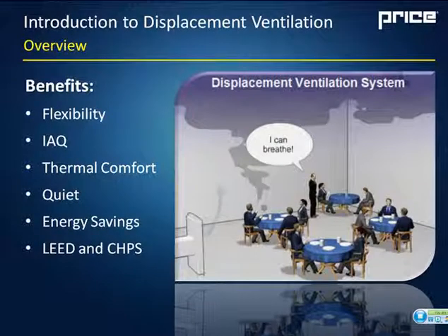A quick summary of benefits here. We're going to go into these at length a little bit later in the presentation, but it's a very flexible system simply because we're not blowing air into the room and we're not driving the room motion with high velocity diffusers. We're now allowing the heat sources to pull the air wherever it's required. Because of the stratification, we also get a significantly improved indoor air quality and thermal comfort as well because of the low velocity and the warmer supply temperatures. Again, because of the lower velocity, the systems are also much quieter, and there are also energy savings and things like LEED and CHPS credits that can be obtained with displacement ventilation.